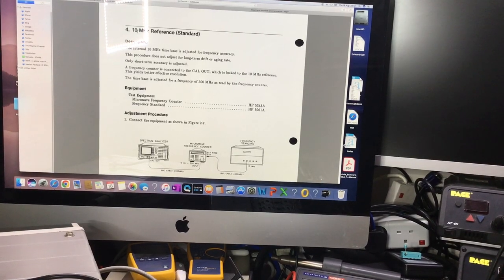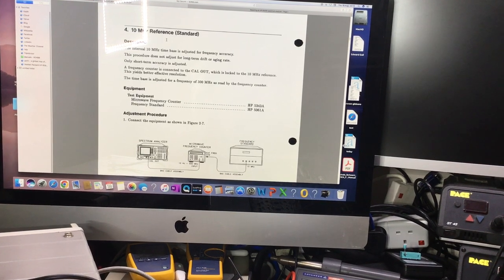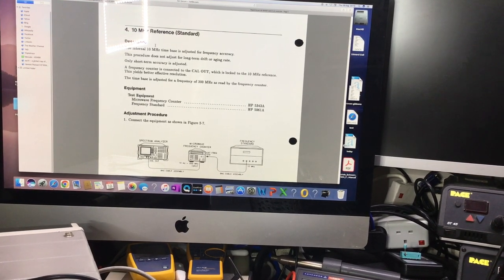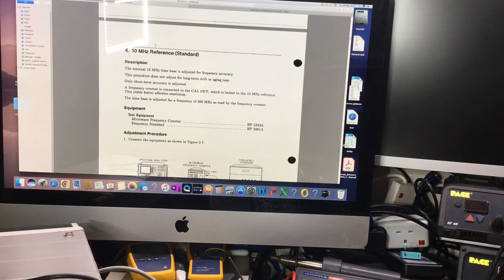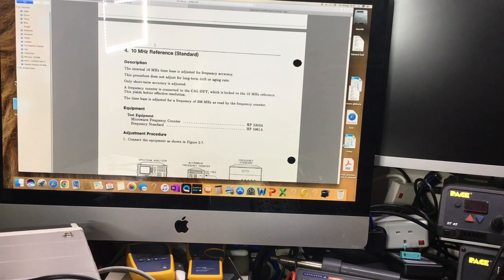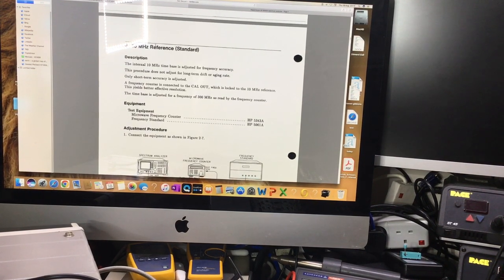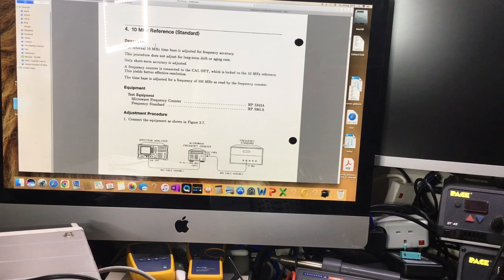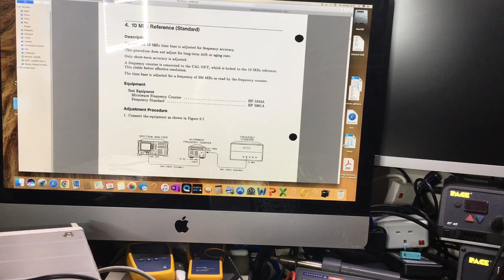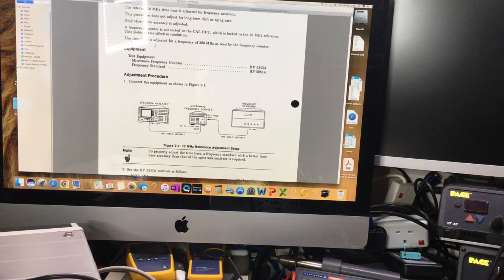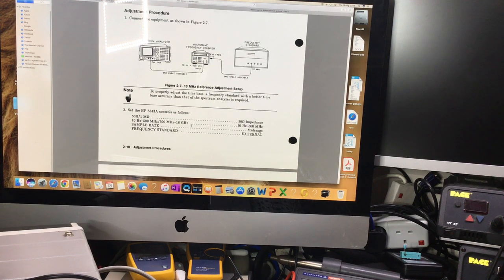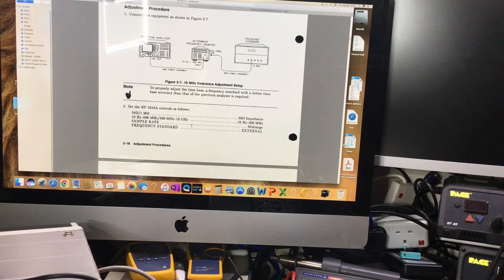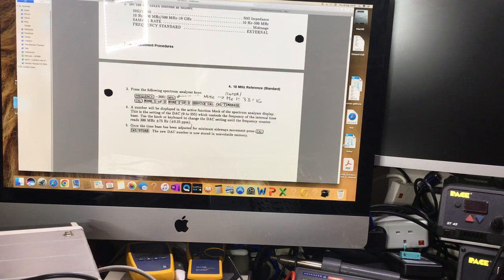So back to the instructions, 10 megahertz reference standard within the unit. The internal 10 megahertz time base is adjusted for frequency accuracy, so it does not adjust a long term drift, blah blah blah. The time base is adjusted for a frequency of 300 megahertz as read by the frequency counter. So it then talks about the test setup, which is the cal output from the instrument into a frequency counter, and then talking about 10 hertz roughly to 500 megahertz range there. Yeah, it talks about a spec.